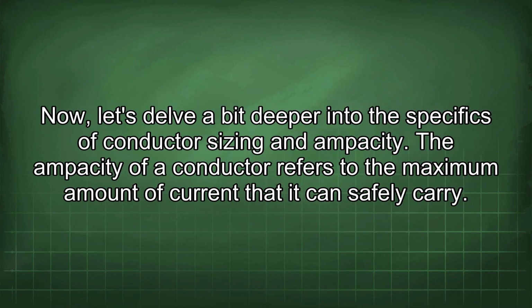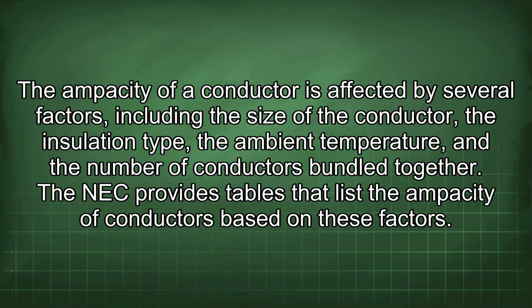Now let's delve a bit deeper into the specifics of conductor sizing and ampacity. The ampacity of a conductor refers to the maximum amount of current that it can safely carry. The ampacity of a conductor is affected by several factors, including the size of the conductor, the insulation type, the ambient temperature, and the number of conductors bundled together. The NEC provides tables that list the ampacity of conductors based on these factors.